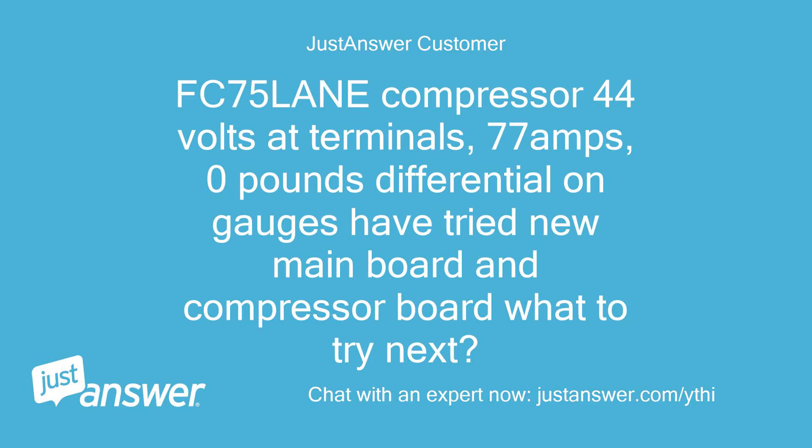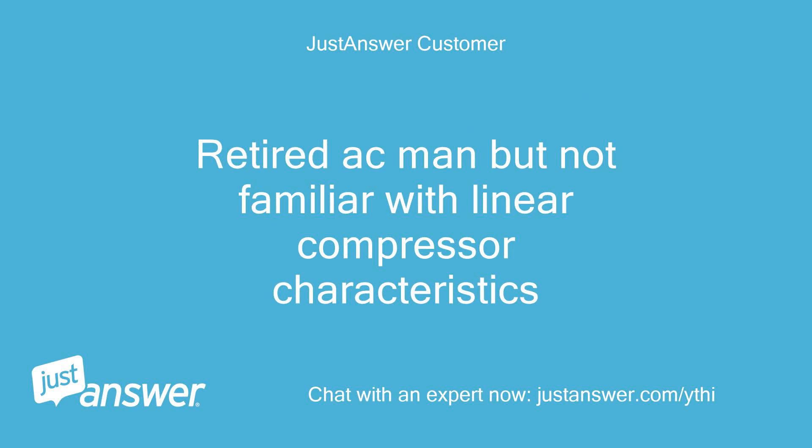FC75LANE compressor: 44 volts at terminals, 77 amps, 0 pounds differential on gauges. Have tried new main board and compressor board — what to try next? Retired AC man but not familiar with linear compressor characteristics.